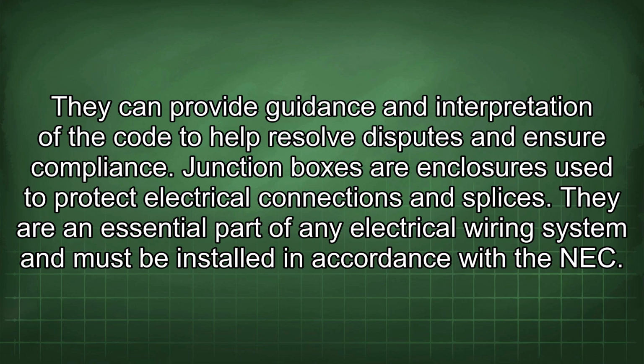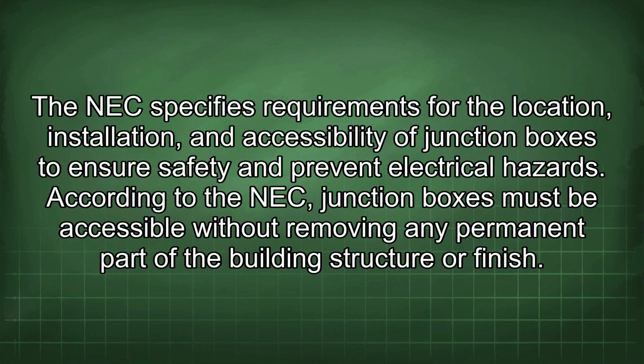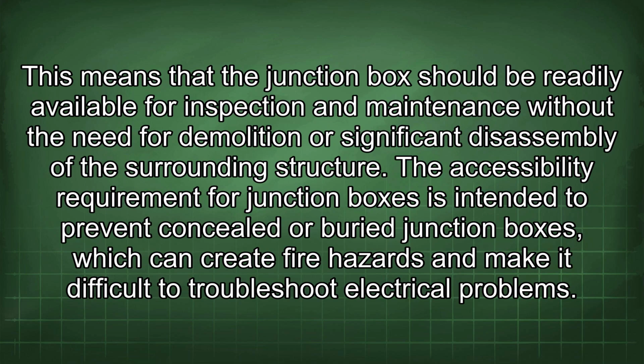They are an essential part of any electrical wiring system and must be installed in accordance with the NEC. The NEC specifies requirements for the location, installation, and accessibility of junction boxes to ensure safety and prevent electrical hazards. According to the NEC, junction boxes must be accessible without removing any permanent part of the building structure or finish. This means that the junction box should be readily available for inspection and maintenance without the need for demolition or significant disassembly of the surrounding structure.